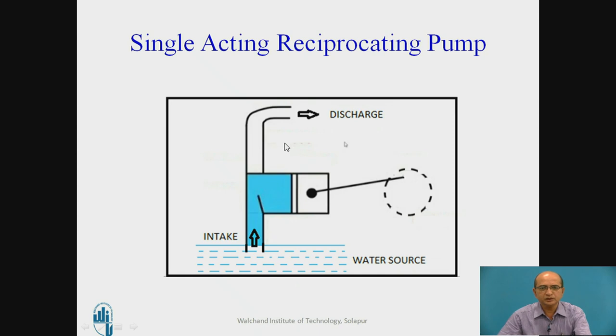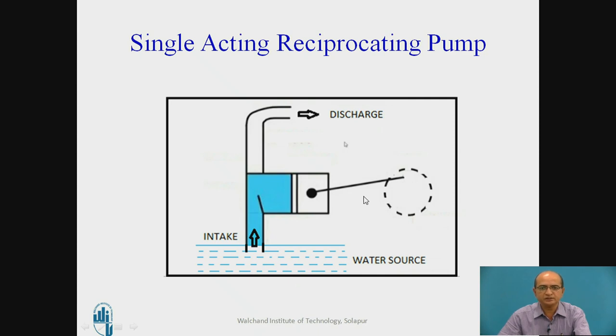Through the delivery pipe, the water is collected in a tank stored at the high level. The piston is connected to the piston rod, which is connected to the connecting rod and crank mechanism. The crank is rotated with the help of an electrical motor, which provides mechanical energy to the reciprocating pump. This mechanical energy is converted into hydraulic energy, pressurizing the water and sending it to the delivery tank.